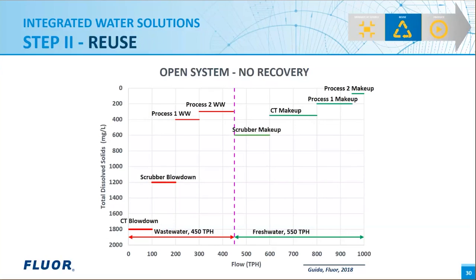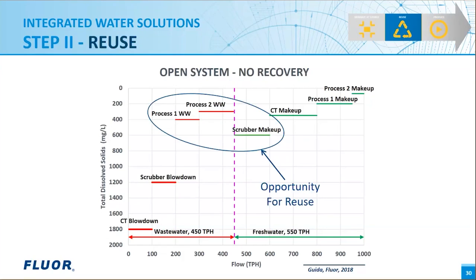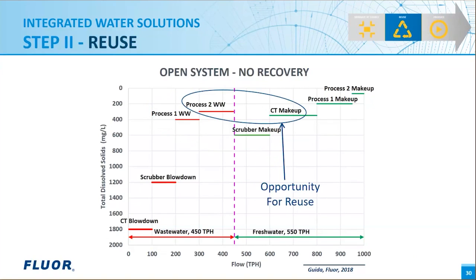The pinch analysis can be used for larger facilities with many streams. It allows for a graphical analysis to make it easier to see opportunities. The analysis provides a way to show flow versus concentration for each stream, for suppliers and consumers. Wastewater from a particular process unit can be considered a supplier if the quality is adequate for another consumer in the facility, either as is without any treatment or with some treatment. On the right, the graph shows minimum water quality requirements and flows for consumers. As you can see, the scrubber makeup can accept a higher TDS than cooling tower makeup. So this makes it a candidate to receive wastewater from process units 1 and 2. However, cooling tower makeup can receive wastewater from process unit 2 only.